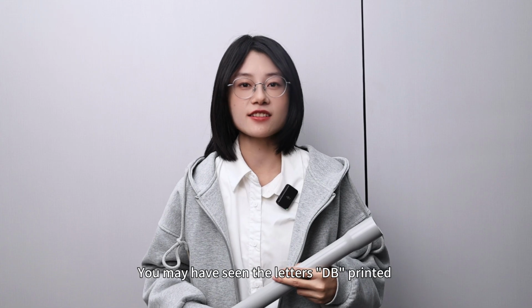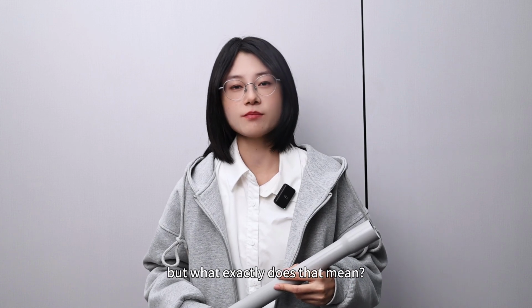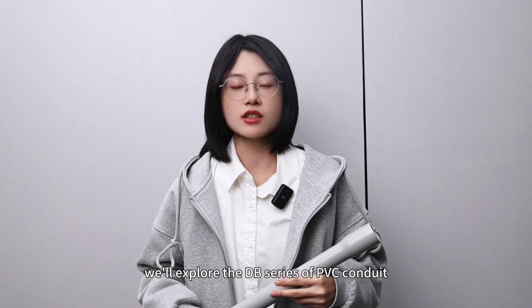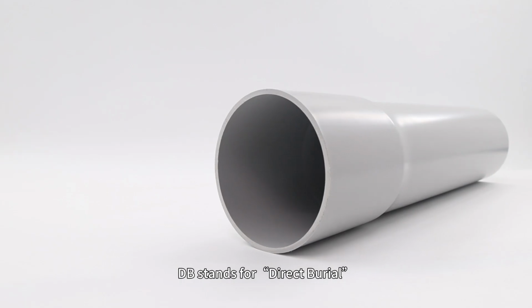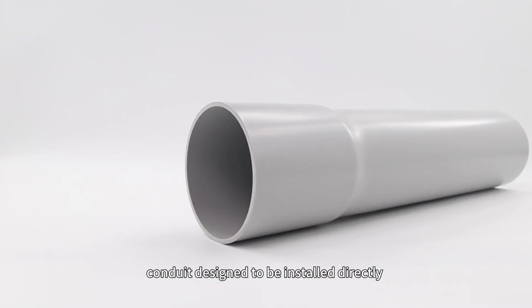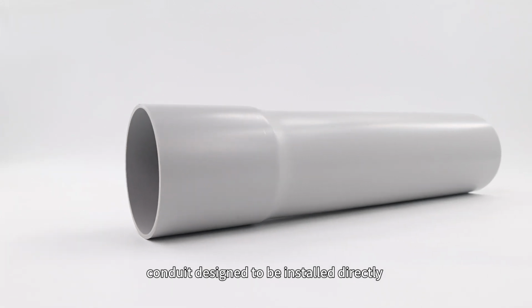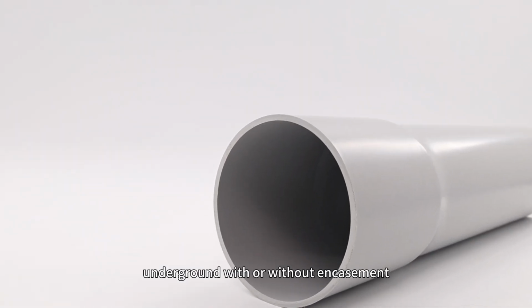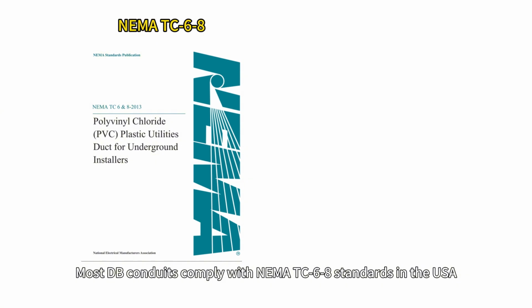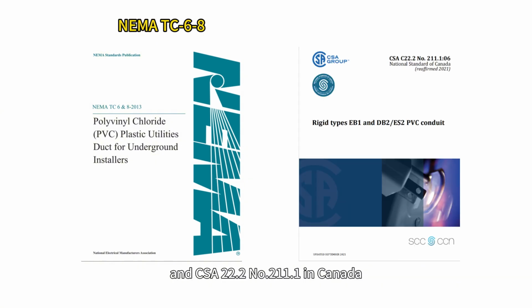You may have seen the letter DB printed on underground conduit, but what exactly does that mean? In this video, we'll explore the DB series of PVC conduit. DB stands for direct burial, conduit designed to be installed directly underground with or without encasement. Most DB conduits comply with NEMA TC 6 & 8 standards in the USA and CSA C22.2 No. 211.1 in Canada.